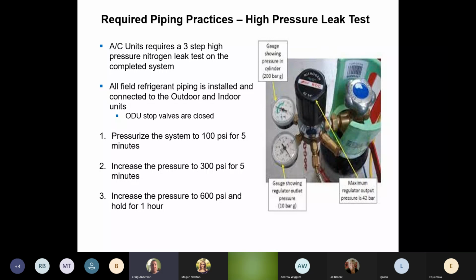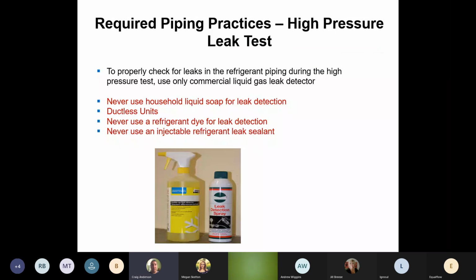So testing for leaks, a lot of guys will throw nitrogen in if we have a leak somewhere in the system. There's special soap out there for refrigeration systems. It's designed for refrigeration systems. It's not going to affect the oils that are in the Freon. Using dish soap, household cleaners, stuff like that, we don't know what kind of effect it's going to have on the oils in the system if it gets in. So buy the right stuff. It's usually in one of the branches. It's made for refrigeration. So when we're checking leaks.